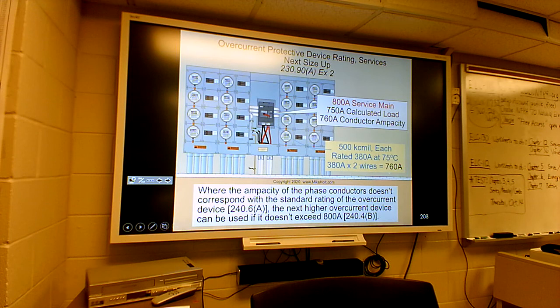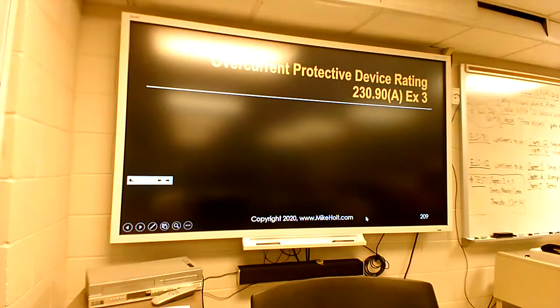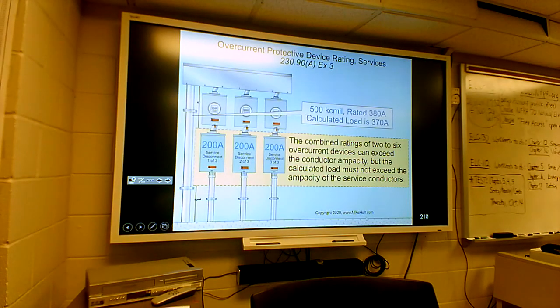So here you've got a difference of 40 amps between 760 and the rating of the breaker, which leaves a little bit of room for danger there, but they allow it. The combined ratings of two to six overcurrent devices can exceed the conductor ampacity, but the calculated load must not exceed the ampacity of the service conductors.